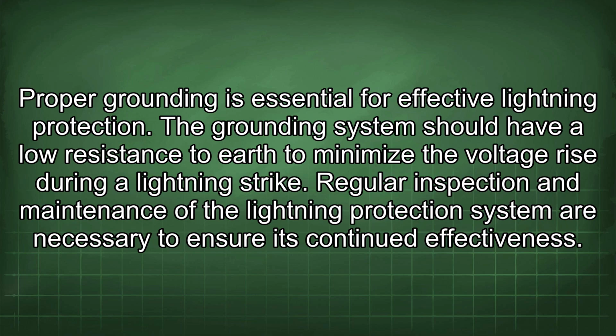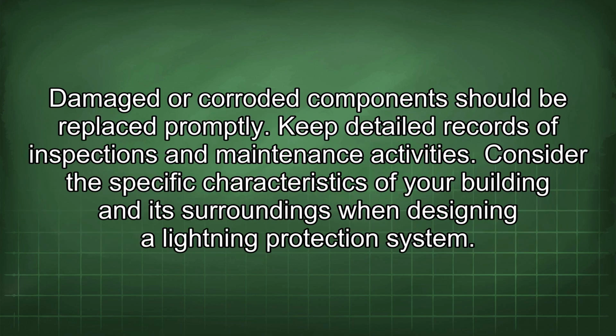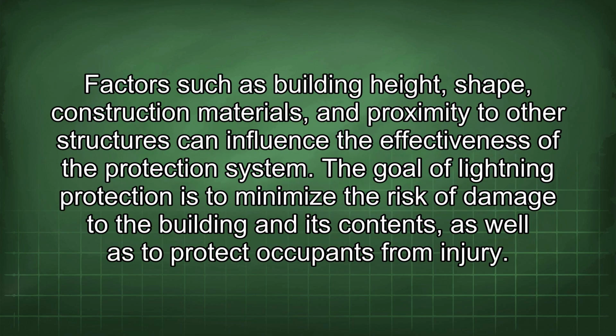Regular inspection and maintenance of the lightning protection system are necessary to ensure its continued effectiveness. Damaged or corroded components should be replaced promptly. Keep detailed records of inspections and maintenance activities. Consider the specific characteristics of your building and its surroundings when designing a lightning protection system. Factors such as building height, shape, construction materials, and proximity to other structures can influence the effectiveness of the protection system.